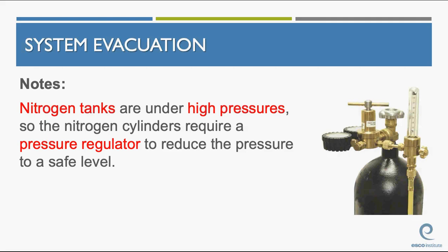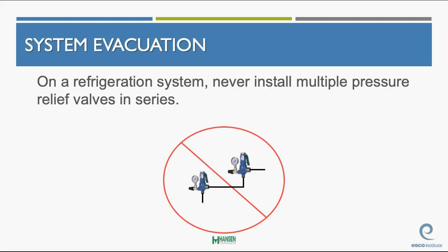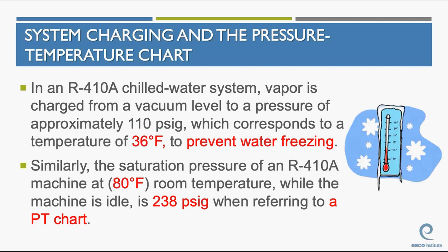Nitrogen tanks are under extremely high pressure, so nitrogen cylinders require a pressure regulator to reduce the pressure to a safe level. You're never going to use a nitrogen tank without a pressure regulator on it. Never install multiple pressure relief valves in series. If you're having a problem with a pressure relief valve going off and leaking, you can't install another one in series with it. You've got to remove the original one and just replace it. Cannot install these things in series. Can only be installed in parallel.